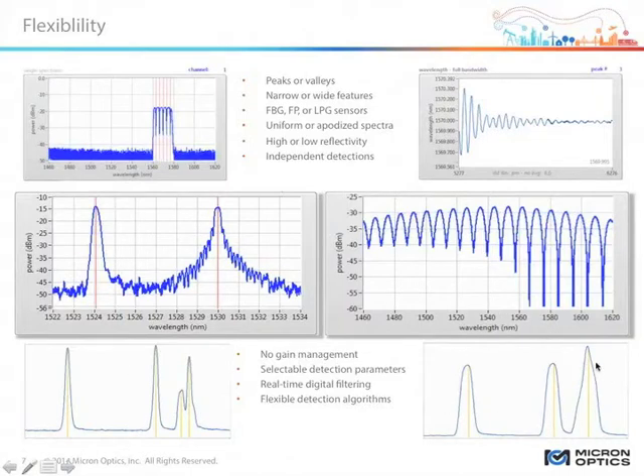So you can see by using the programmable real-time digital filtering, I can change the way the instrument perceives that FBG. So I can effectively change the resolution of the instrument on this one particular channel, leaving the rest of my channels at a high precision, high resolution like we might have for this Fabry-Perot sensor. But on this channel, I'll increase the digital filtering and really resolve that as just one robust peak that I can detect over a wide variety of conditions. So those are a couple of examples of the flexibility of the si255.